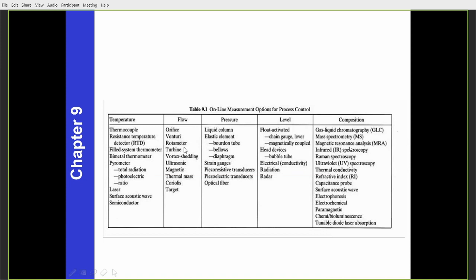One of the reasons is that usually you need to know what you are measuring. Are you measuring, for example, the velocity of a gas or a liquid, or the temperature of a gas, liquid or maybe a solid? And once you know the medium, you need to know whether this gas or liquid is corrosive or not. Fluid consists of gas or liquid. So let's say you are measuring temperature in a corrosive environment. In this case, you cannot use an instrument made of steel, but probably need to choose one made of stainless steel because it can withstand the corrosive nature of that fluid.